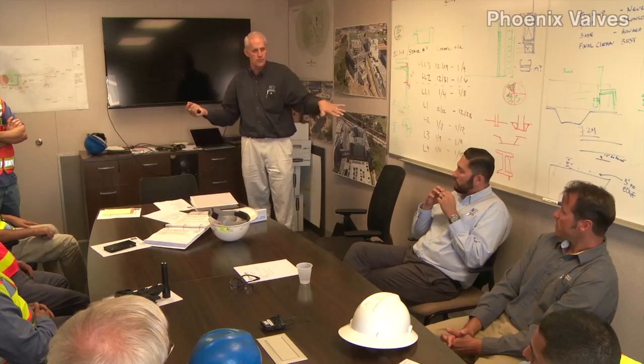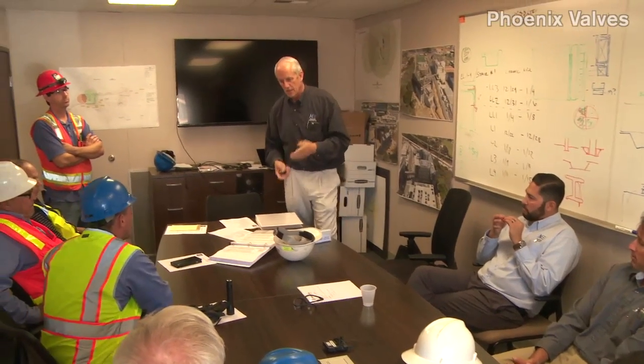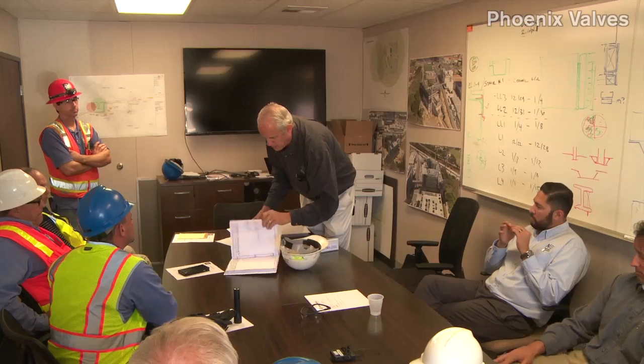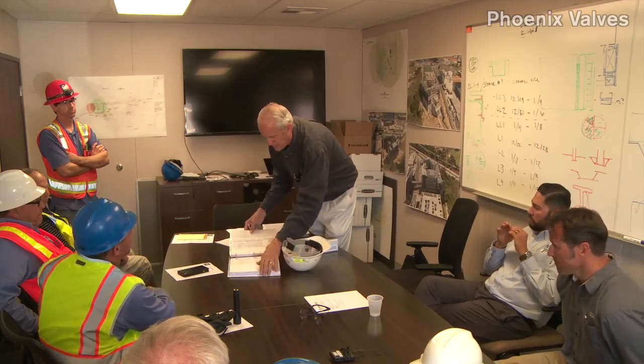They send a switch via BACnet to our system, and so we've checked that out. We've rung that whole part out with Johnson. Yeah, the balancers actually, when they did the balancing, they had Johnson switch it to do their test. So we didn't do an artificial switch just by putting a jumper in on our controller. We actually had to go through the Johnson system. So it's been rung out all the way through. So the startup sheets tell you every room we've been to, what we measured, what we found in every room.